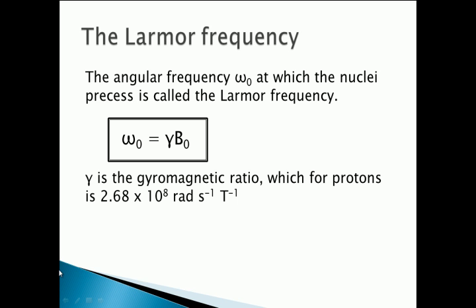The protons precess at a certain angular frequency given the symbol ω₀, called the Larmor frequency. ω₀ depends on two things: gamma, the gyromagnetic ratio, and the strength of the external magnetic field B₀. The gyromagnetic ratio is a constant for any particular particle with spin, and for protons it has the value 2.68 × 10⁸ radians per second per tesla. B₀ is measured in tesla and ω₀ in radians per second. Magnetic field strengths in MRI machines are typically around 1 to 2 tesla, so the Larmor frequency is roughly the same order as the gyromagnetic ratio — hundreds of millions of radians per second.